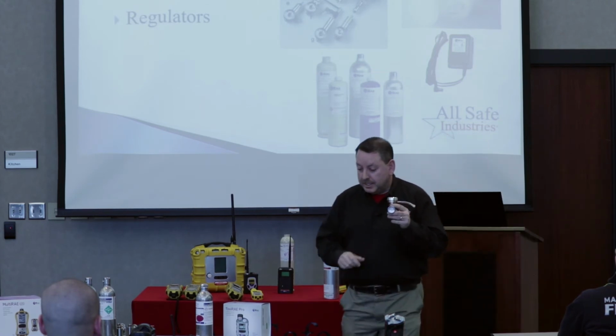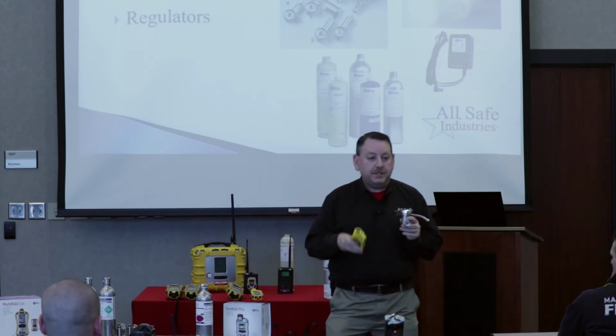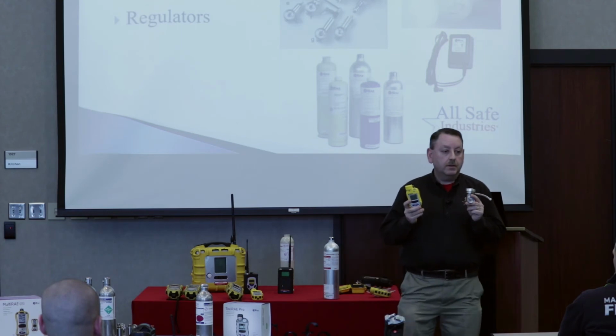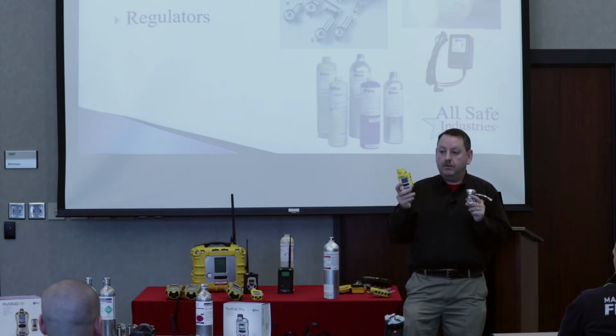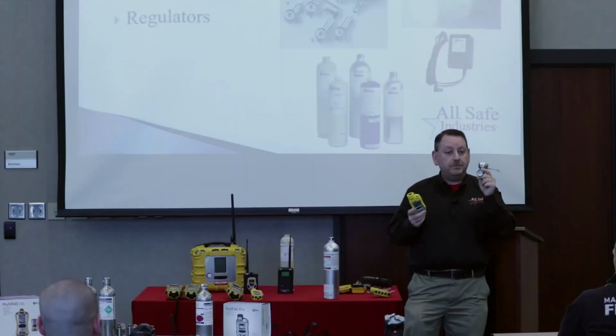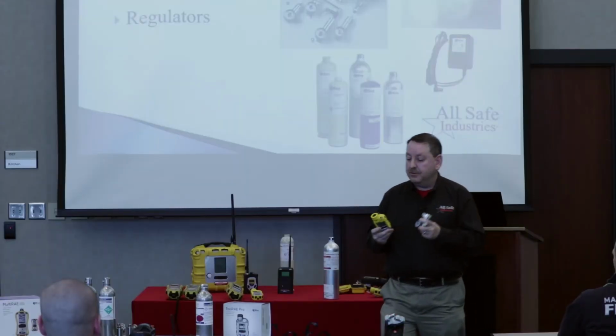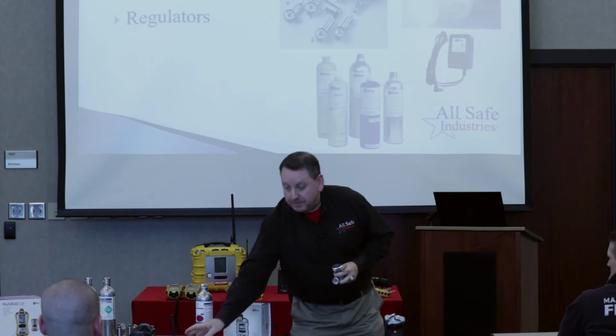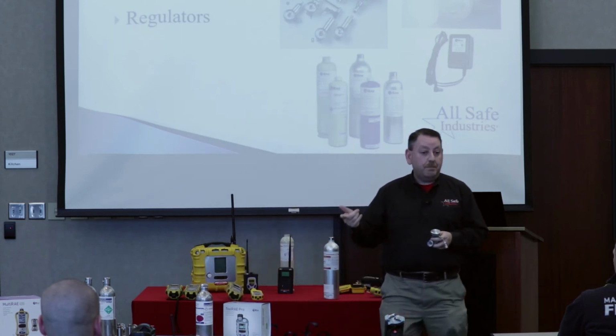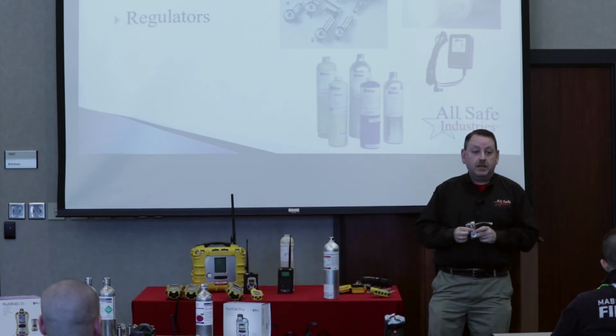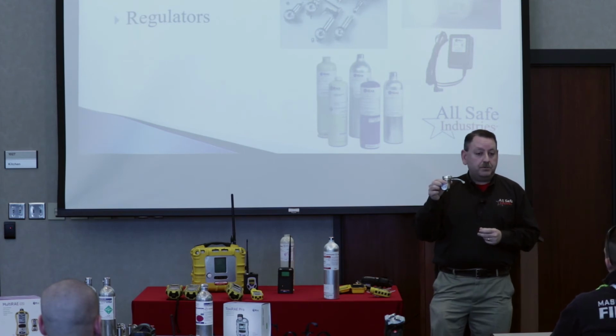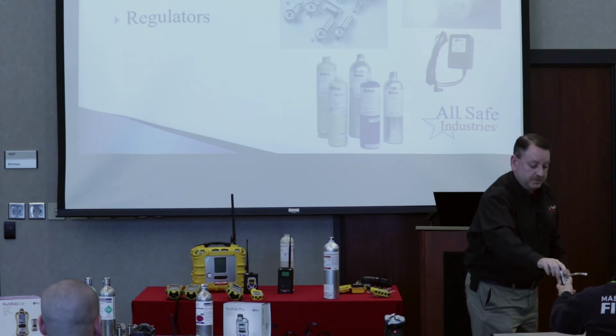So, can I use this regulator with this meter? No. Why? There's no pump. Great. There's no pump on this one, so I wouldn't be able to extract the gas through the demand flow regulator. You would want to use a preset flow rate regulator if you were doing a manual calibration on your single gas. The demand flow is only for pumped instruments or through a calibration cradle. Okay, so I'll pass that around too.